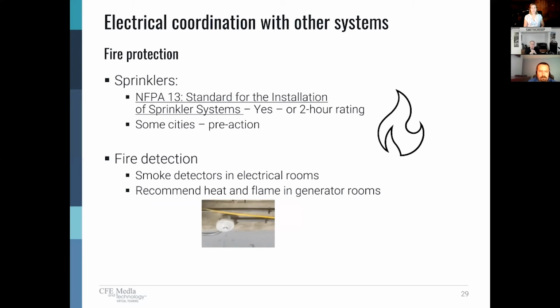There are a few cities that require pre-action on the main disconnecting service. Those are rare, but I have run into them. They're just simply trying to avoid accidental water. It's certainly a good engineering practice. It's just a lot of money to put in a pre-action or dry type pipes in your main switchgear room. As far as fire detection, you want smoke detectors in your primary electrical rooms. And then in generator rooms, obviously you can't use smoke. You're going to look at heat or flame detection. Next.